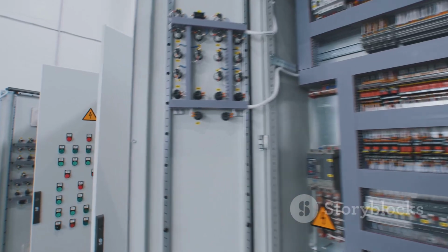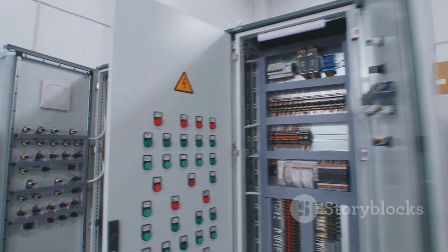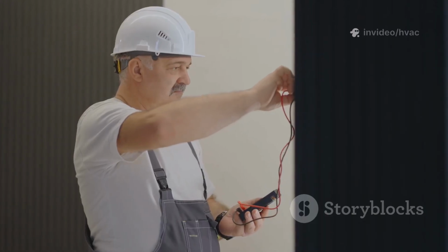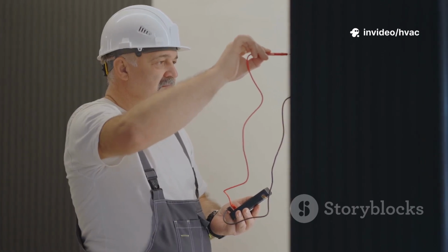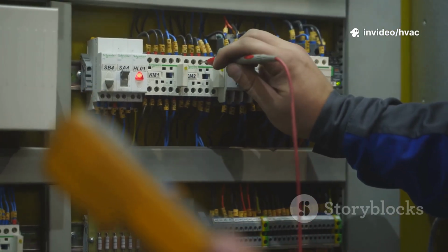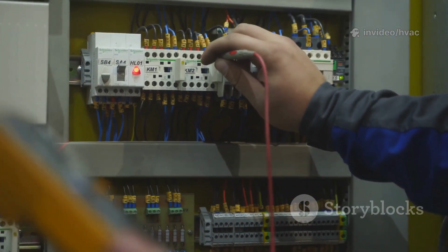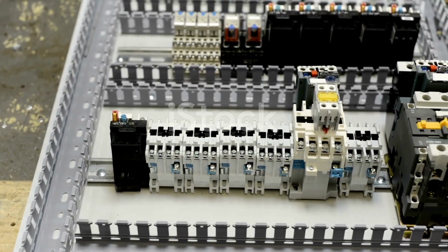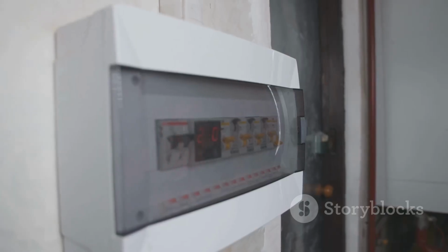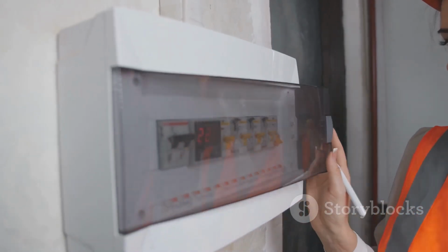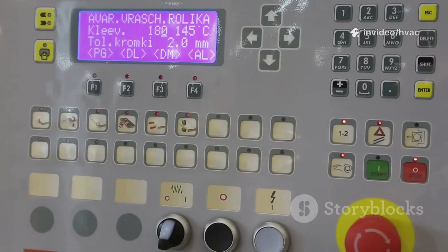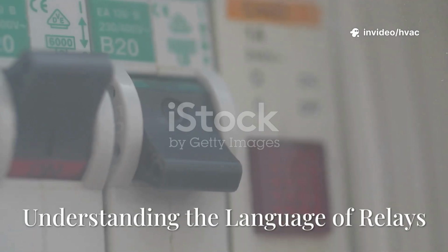Multiple safety devices can be wired in series, creating a chain of permissions. If any safety isn't met, the relay stays open and the equipment stays off. This makes control wiring logical, safe, and easy to troubleshoot. Relays are the building blocks of every interlock chain. They keep systems safe by enforcing the rules automatically. That's how we build reliable, safe HVAC controls.